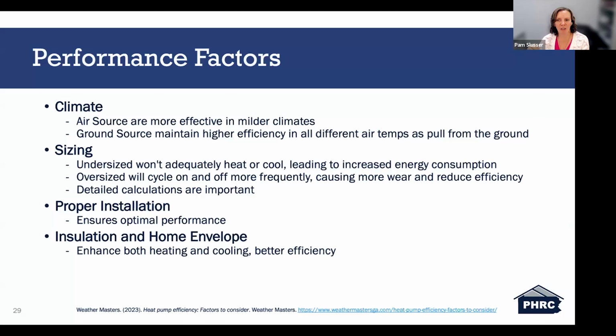The importance of having an HVAC professional size the unit is extremely crucial because they are the professional and they understand what they're doing. If you install an undersized unit, it's not going to adequately heat or cool the home, which will lead to increased energy consumption. And if you install an oversized unit, it's going to cycle on and off more frequently, causing unnecessary wear or reducing the efficiency as well.